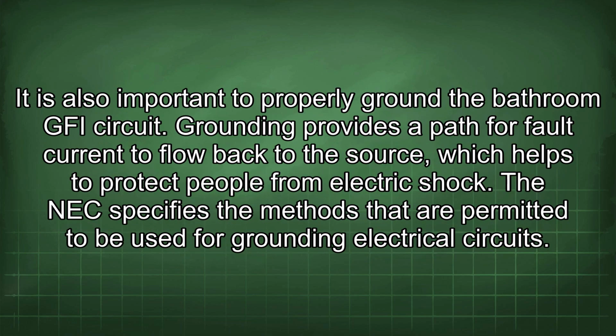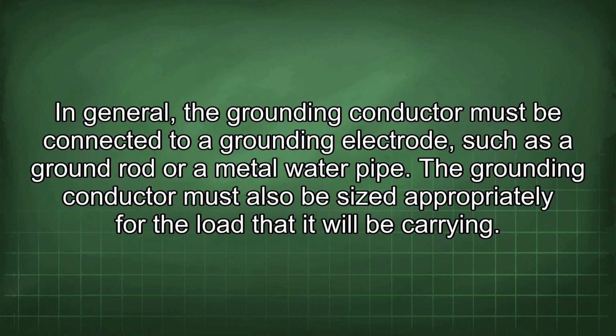It is also important to properly ground the bathroom GFI circuit. Grounding provides a path for fault current to flow back to the source, which helps to protect people from electric shock. The NEC specifies the methods that are permitted to be used for grounding electrical circuits. In general, the grounding conductor must be connected to a grounding electrode, such as a ground rod or a metal water pipe. The grounding conductor must also be sized appropriately for the load that it will be carrying.